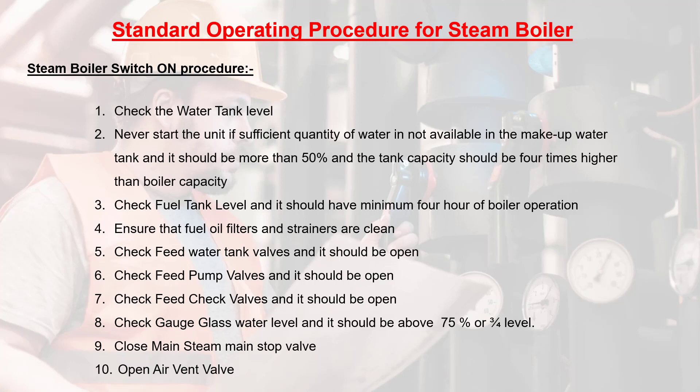Step 1: check the water tank level. Step 2: never start the unit if a sufficient quantity of water is not available in the makeup water tank — it should be more than 50%, and the tank capacity should be four times higher than boiler capacity. Step 3: check fuel tank level and it should have a minimum of four hours of boiler operation.